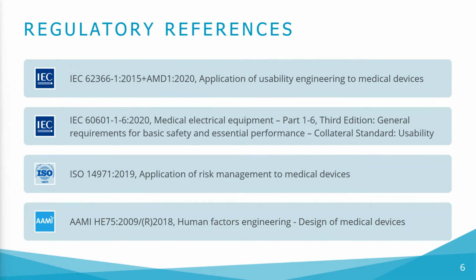There are some international consensus standards involving HFE and regulatory references to follow, which are IEC 62366-1 2015 plus Amendment 1 2020, Application of Usability Engineering to Medical Devices, IEC 60601-1-6 2020, Medical Electrical Equipment Part 1-6, 3rd edition, General Requirements for Basic Safety and Essential Performance, Collateral Standard Usability, ISO 14971 2019, Application of Risk Management to Medical Devices, AAMI HE75 2009, reaffirmed 2018, Human Factors Engineering Design of Medical Devices.